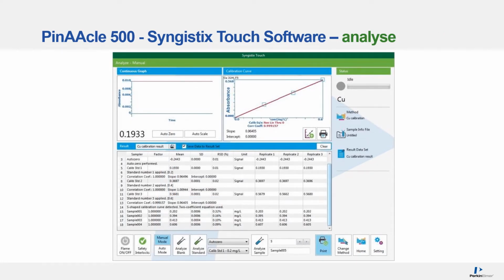Once you have clicked on that Analyze button, you would be presented with this final screen. This screen will show you a real-time continuous graphics screen in the top left-hand corner. In the top central area, we would have an updated calibration curve. So in real time, as you're analyzing calibration standards, we'll update your calibration curve and give you your correlation coefficients. And then in the middle bottom portion of the screen, you'll have a full list of all the samples that you have analyzed, along with the replicates, the RSD, the standard deviation, and the mean. And then in the bottom portion of the window, you'll have all of the functionality buttons.